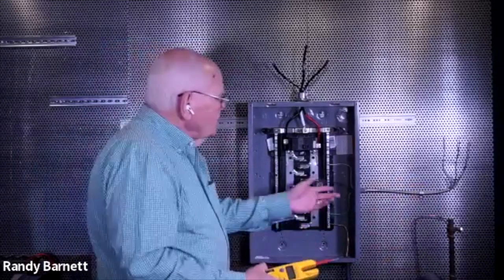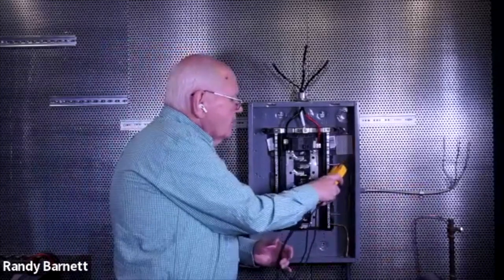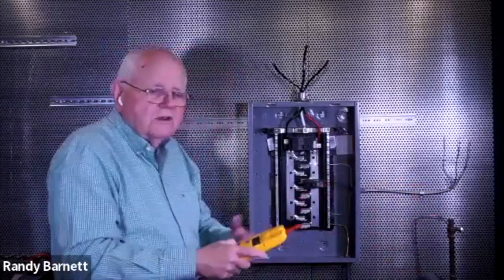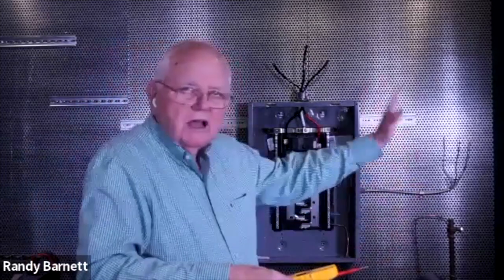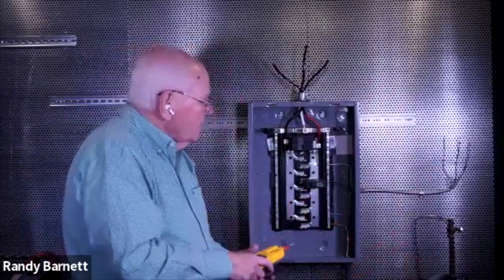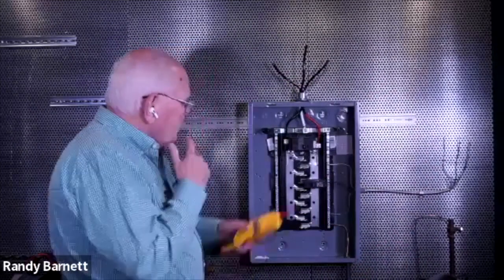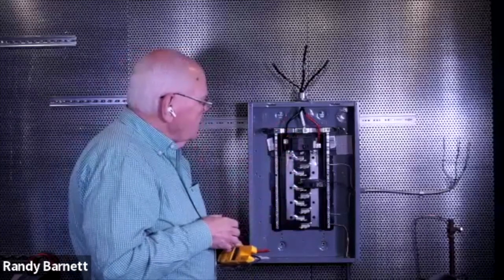Now, as far as sizing the ungrounded and the grounded conductors going out to my load, that's based on my load calculations, right? And whatever it is I'm supplying, I have to look at the 100% of non-continuous and 125% of continuous loads and things like that. Whatever rules I'm following there determine the size conductors that I need for my circuit. Some tables for sizing these conductors.